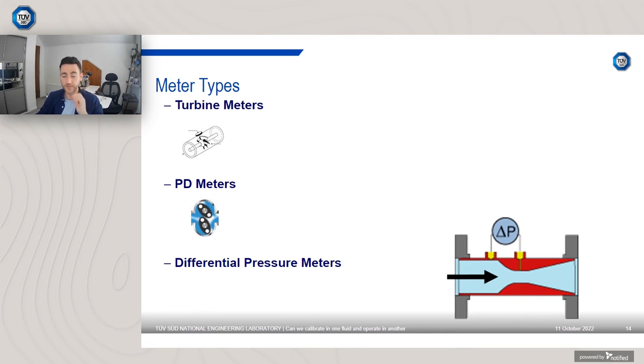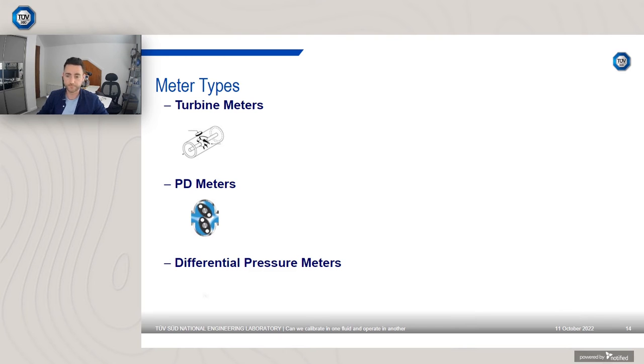Then we have differential pressure meters. Now these are different, there's no moving parts here. We're discussing DP meters such as an orifice plate, venturi, wedge, cone meter. They have no moving parts and they actually are suitable for both liquid and gas use, depending upon your differential pressure transmitters. You have to make sure they're suitable for liquid or gas use, or both, depending on which fluid you're using. But there should be no reason you couldn't use a differential pressure meter in water and then use it in gas as well. So DP meters, different from turbine and PD, can be used in both fluids.